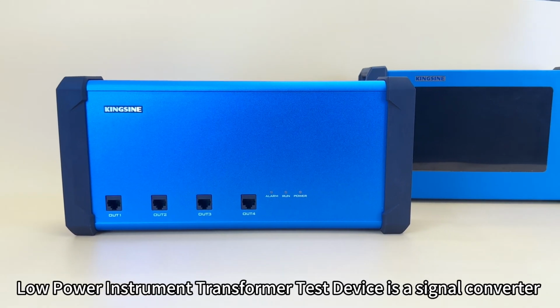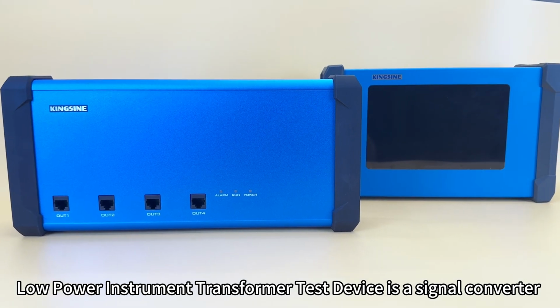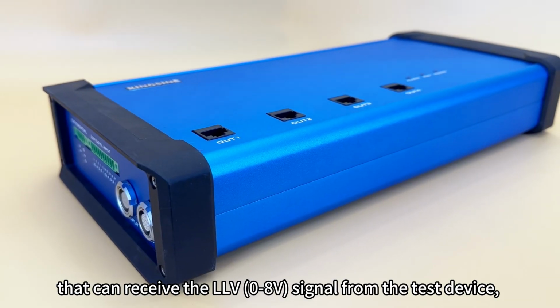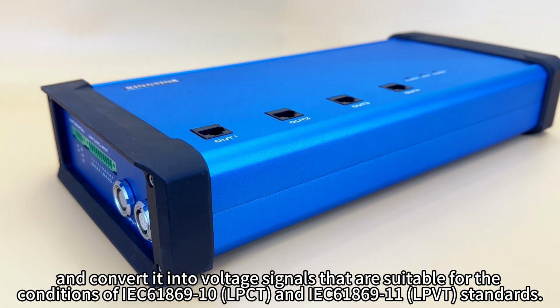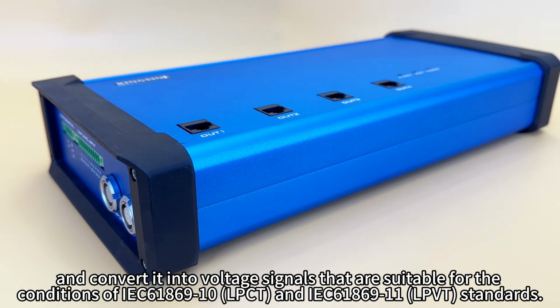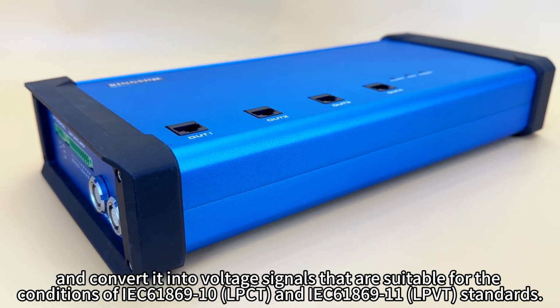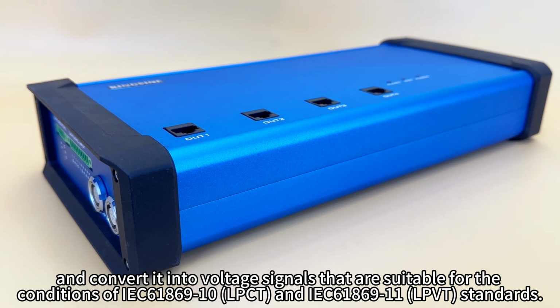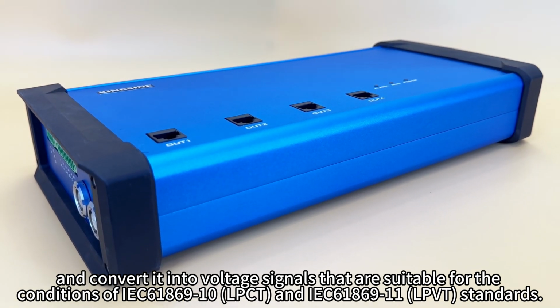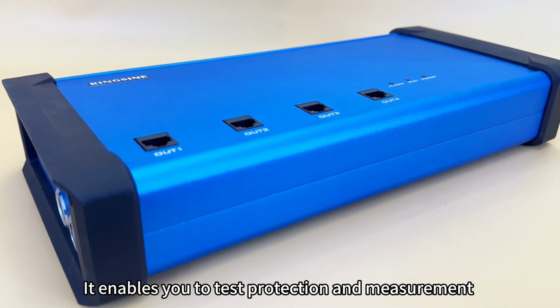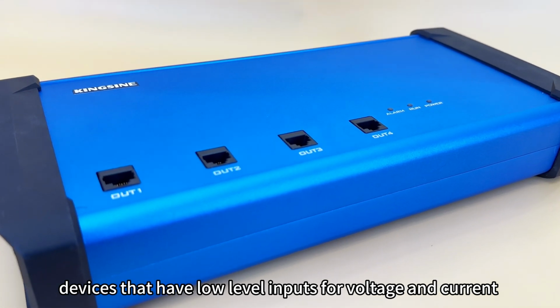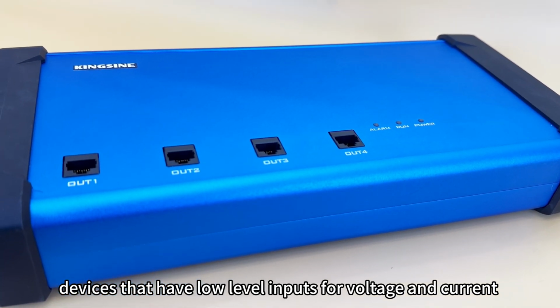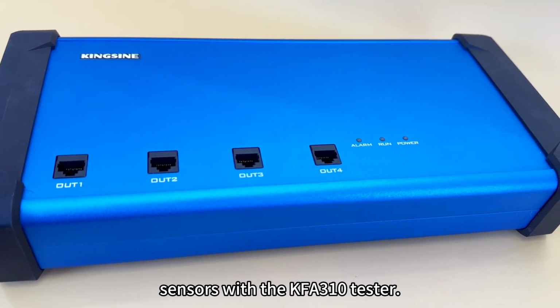The low power instrument transformer test device is a signal converter that can receive the LLV signal from the test device and convert it into voltage signals suitable for the conditions of IEC 61869 Part 10 and Part 11 standards. It enables you to test protection and measurement devices that have low-level inputs for voltage and current sensors with the KFA310 tester.